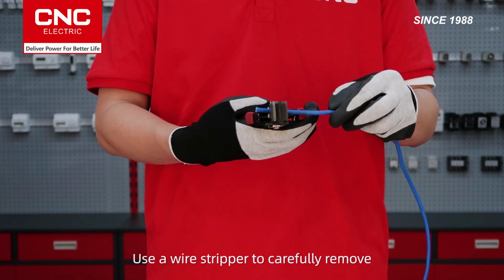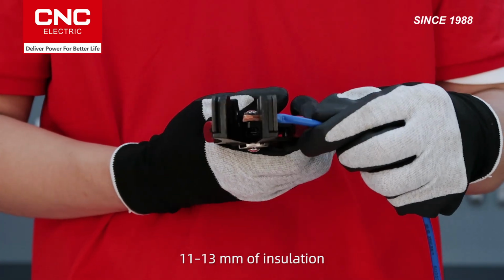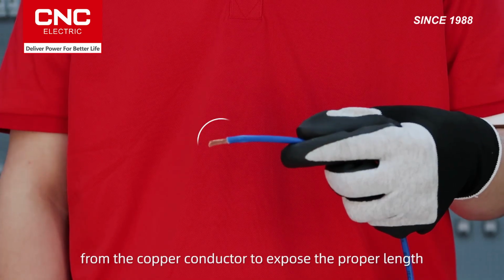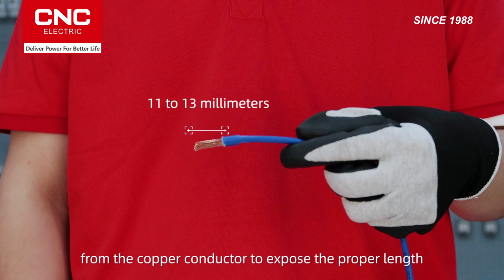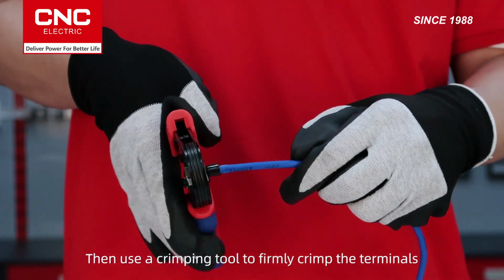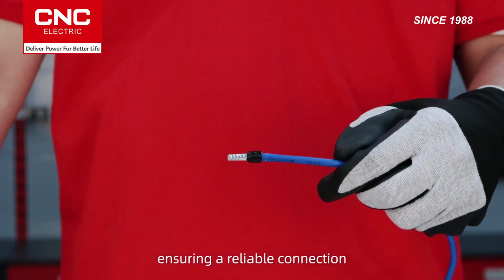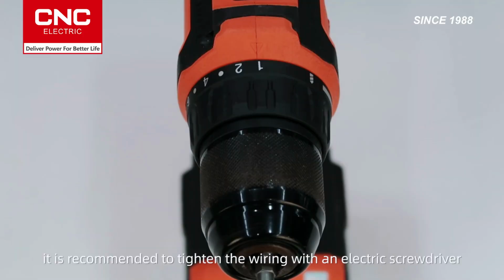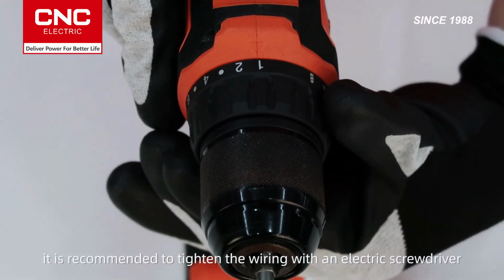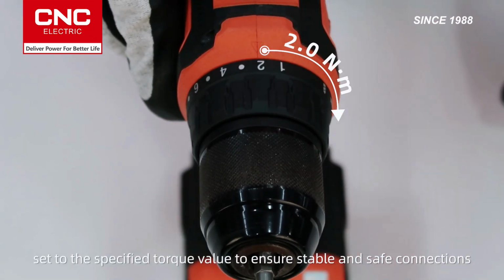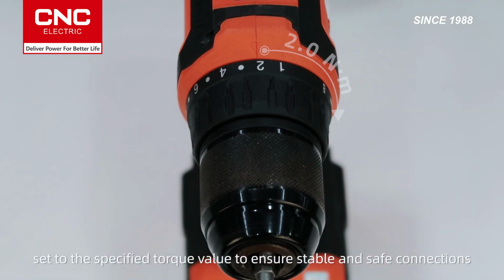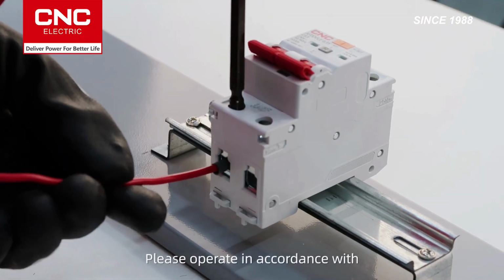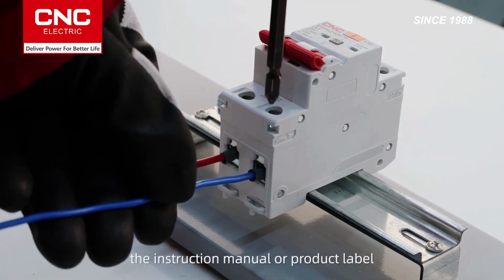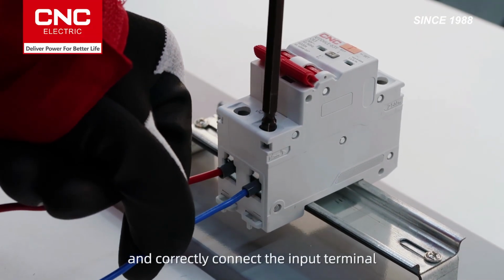Use a wire stripper to carefully remove 11-13 mm of insulation from the copper conductor to expose the proper length. Then use a crimping tool to firmly crimp the terminals, ensuring a reliable connection. Finally, it is recommended to tighten the wiring with an electric screwdriver, set to the specified torque value to ensure stable and safe connections.